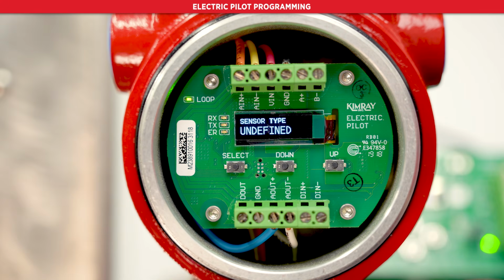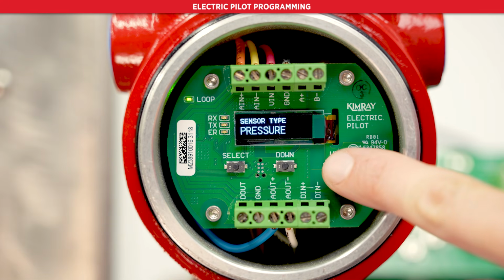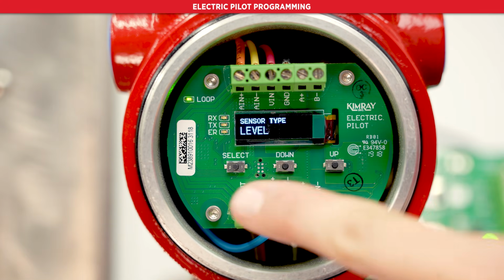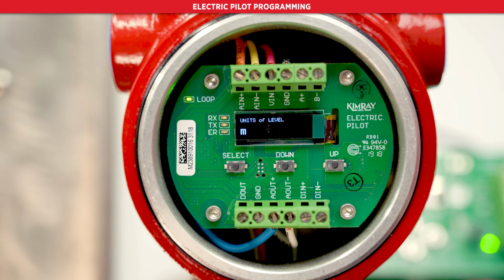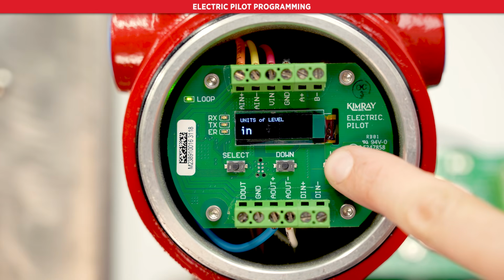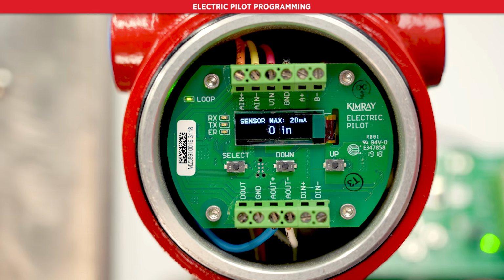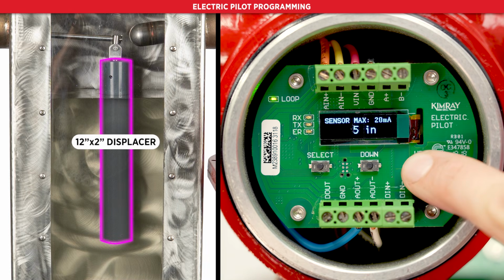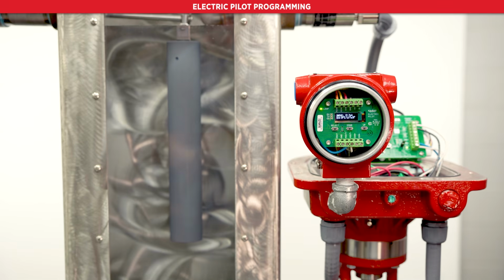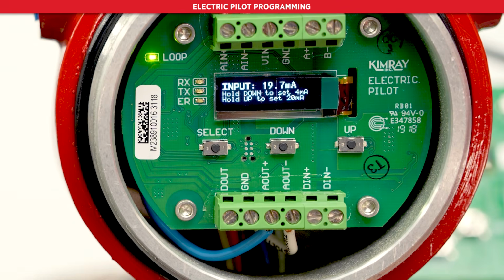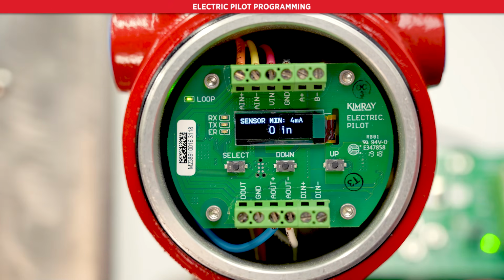The pilot should say, "Sensor type undefined." Push up or down to get to level, then press select. The next screen will ask you for the units of measurement. We'll select inches, then press select. Next, we'll set the sensor maximum, which will be the 20 milliamp output. Because we have a 12-inch displacer, we'll select 12 and press select. That will set it so 20 milliamp is the output when the displacer is entirely submerged. The sensor minimum is where the 4 milliamp output will be, which will be set to 0.